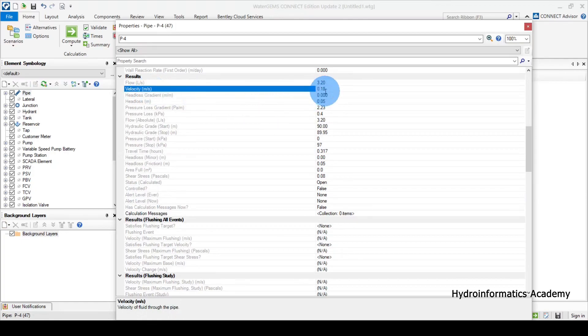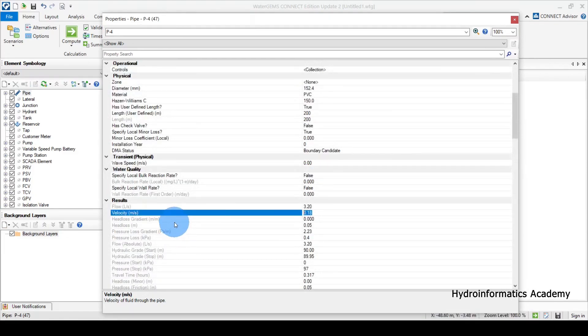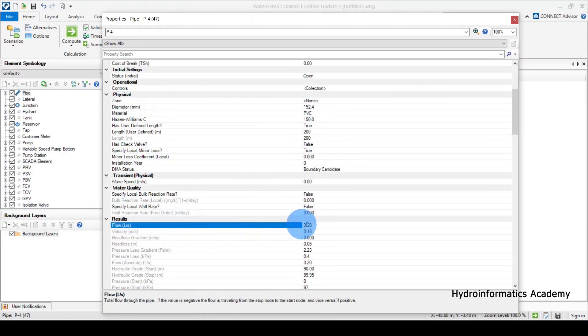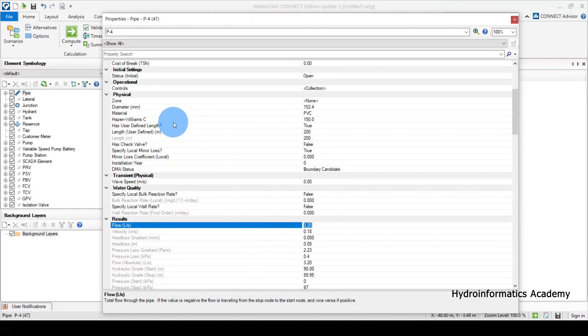The most important value here is velocity. We have 0.18 meters per second. Remember, we need to aim for a minimum velocity of 0.4 to 0.5 all the way to 1.5 meters per second. This value of 0.18 is quite small, which suggests the pipe diameter is quite big compared to the flow we want to carry. So we need to find a mechanism to increase head losses and hence increase velocity — the best way to do that is to reduce the pipe diameter.